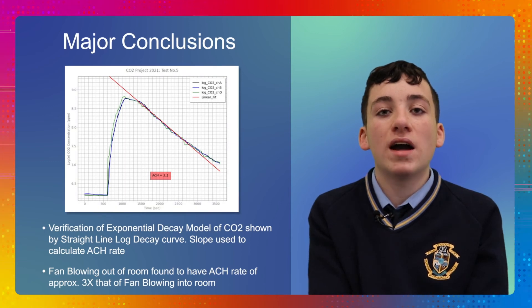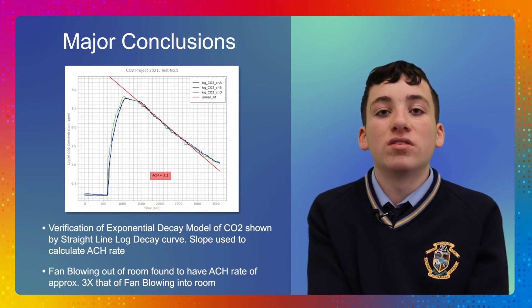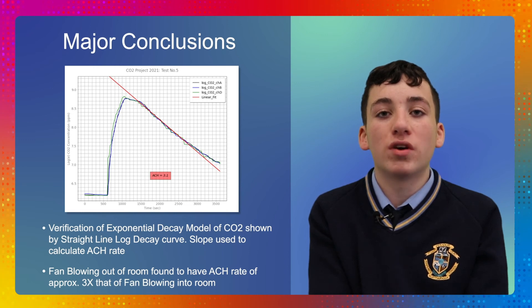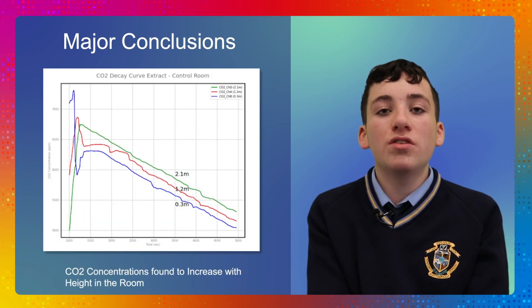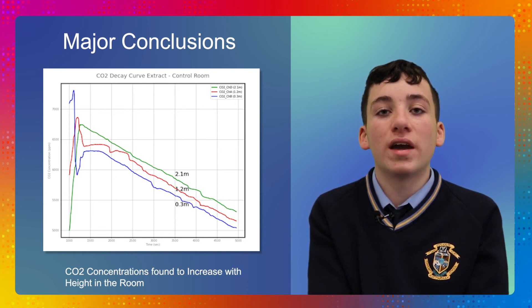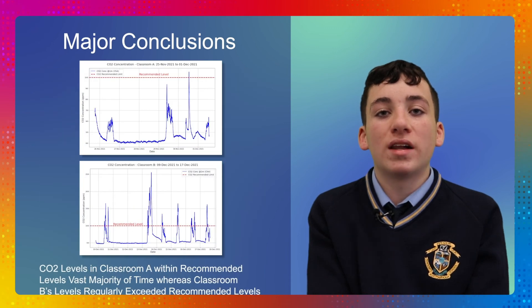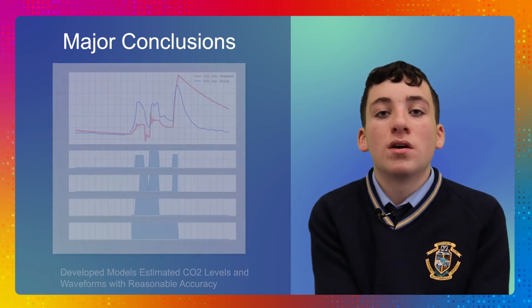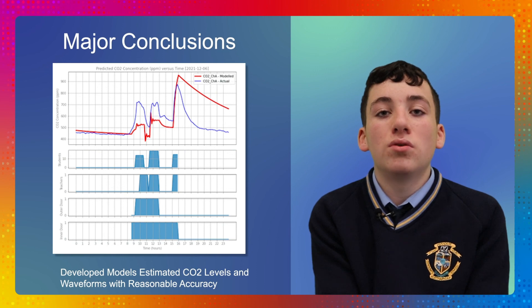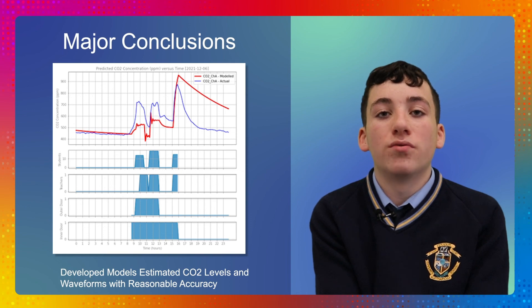It was found that both the passive and fan-assisted active ventilation techniques followed the standard exponential decay model of CO2 concentration, and that fans blowing air out of rooms gave an ACH rate of approximately three times that of fans blowing air into rooms. CO2 concentrations were found to, in fact, increase with height, and this is an inversion of the stratification of CO2 that might be expected. The CO2 levels in classroom A were within recommended levels the vast majority of the time, whilst in classroom B the CO2 peaks consistently exceeded these levels. The models developed predicted CO2 levels with reasonable accuracy and gave good qualitative predictions of CO2 concentration waveforms.